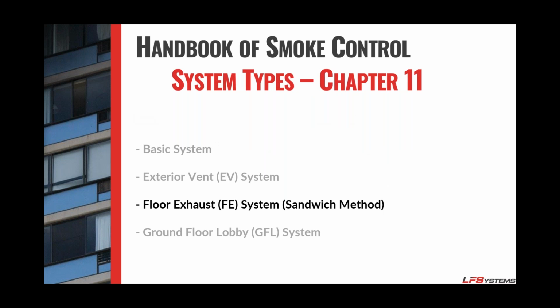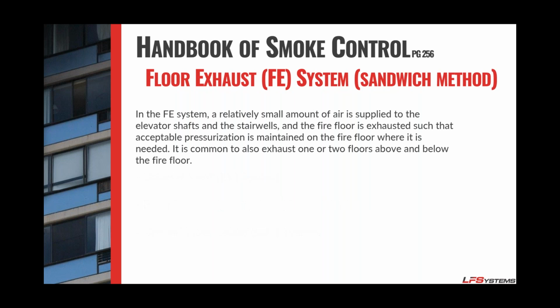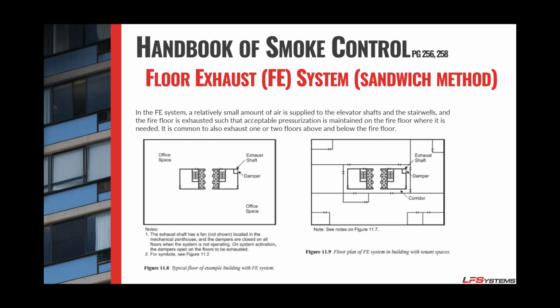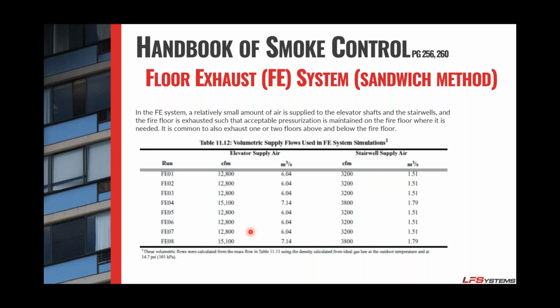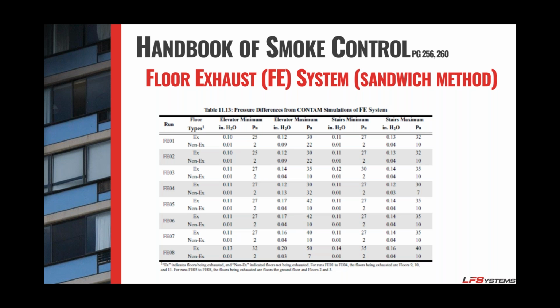Probably one of the most common that we see is the floor exhaust system or the sandwich method. This is really big, especially down in the Southeast. In the floor exhaust system, it actually uses less makeup air supplied in the shafts and the stairwells, but it also uses an exhaust fan to exhaust the fire floor, and typically a floor or two above it or below. And the concept assumes that you're exhausting smoke, so therefore you don't need as much air in the system, because if there's less smoke in the building, it's less chance of it propagating. The chart is showing that yes, you do drop almost by half the amount of air needed to supply it. And it is a successful system in the analysis.